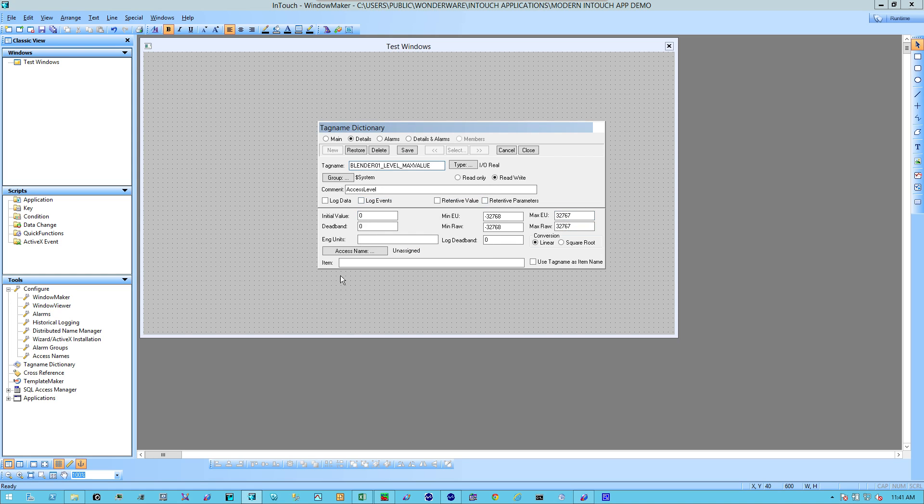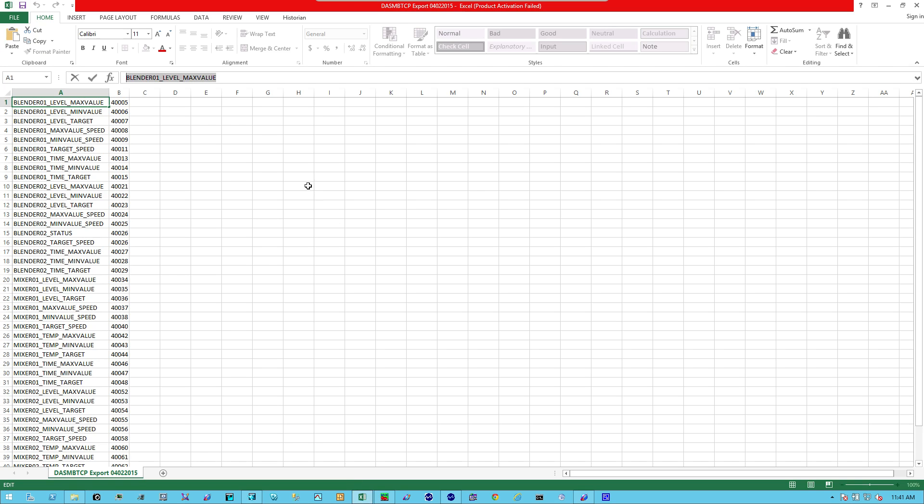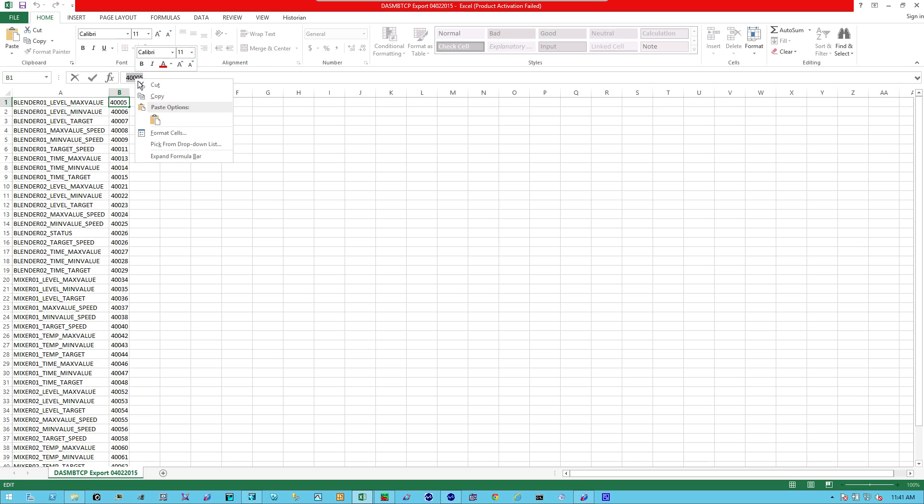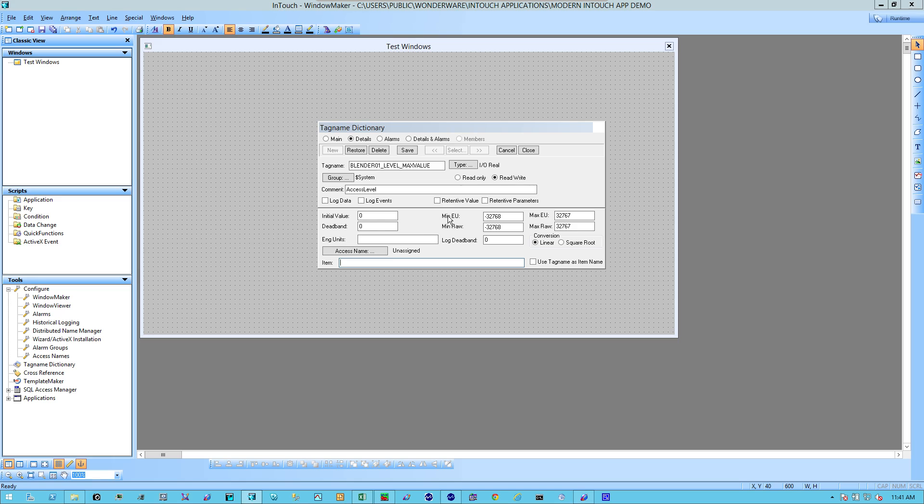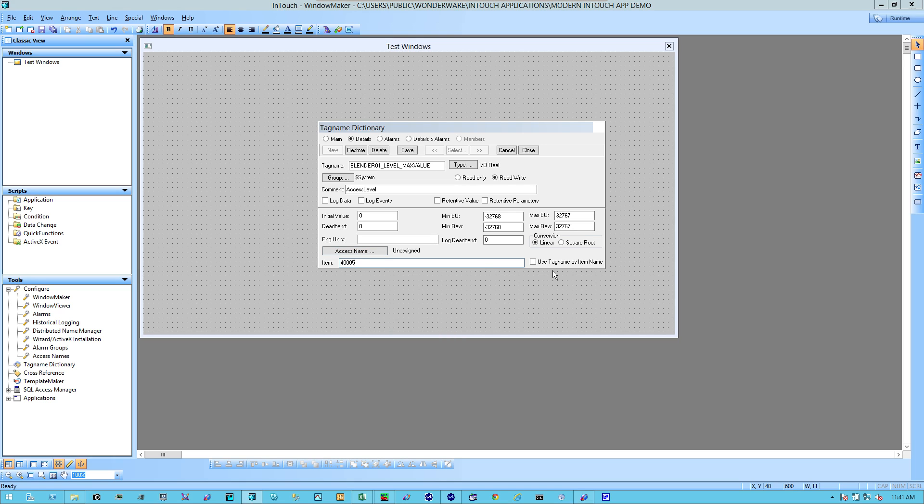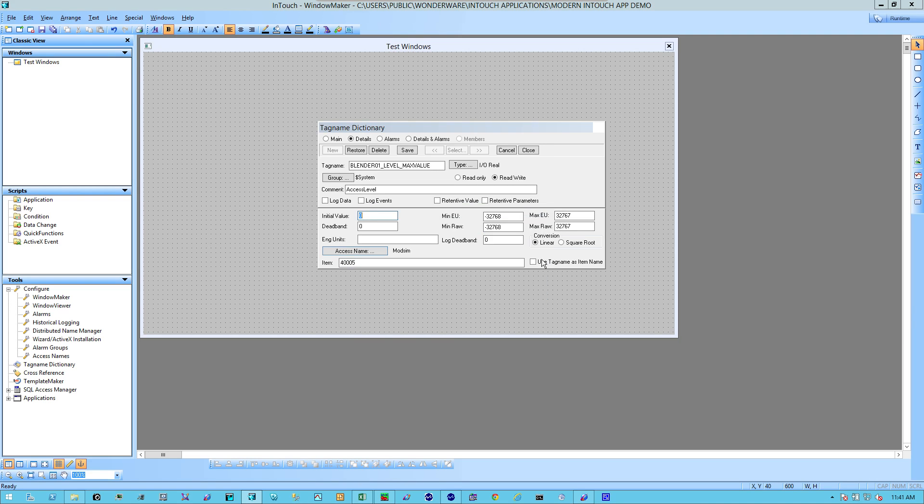As far as the item reference, head on back to my Excel spreadsheet. The item reference is 40,005. That's the registry address. Head back to InTouch and I'm going to put that value here. And under the Access name, I'm going to select Mod Sim. Select Close.